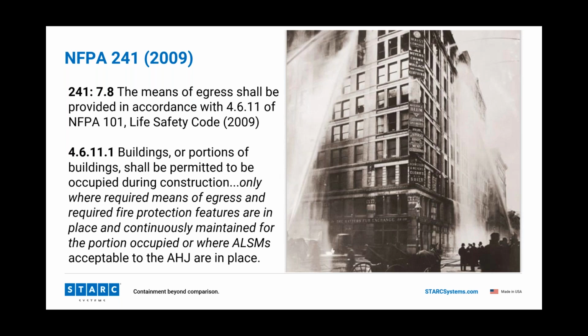you have to implement alternative life safety measures, ALSMs, which if you're a Joint Commission hospital or you've heard of Joint Commission, you've probably heard it called ILSMs, interim life safety measures, same thing, same terminology. What it means is that when we reduce the level of life safety in the building below the requirements of the Life Safety Code in NFPA 101, we have to assess if alternative measures are necessary, and if so, we have to implement those measures.